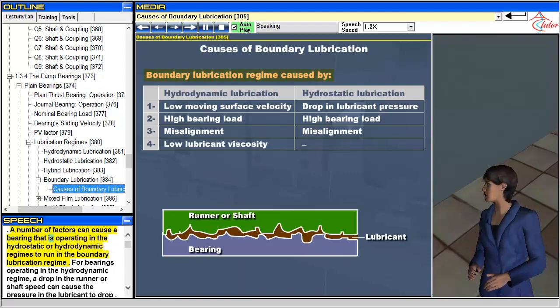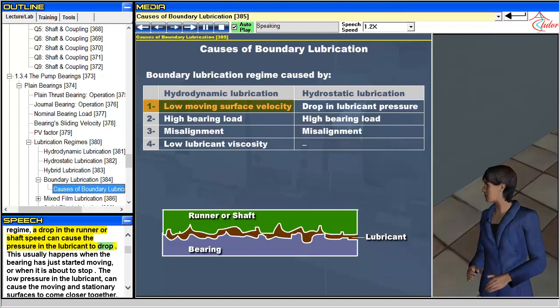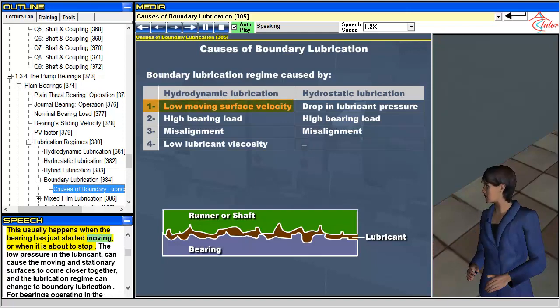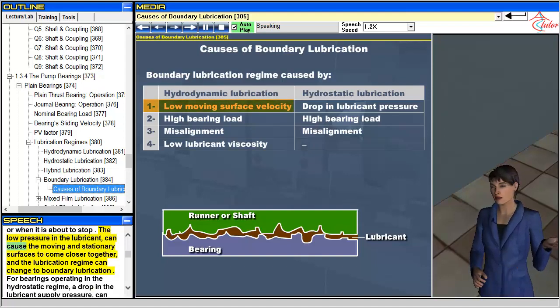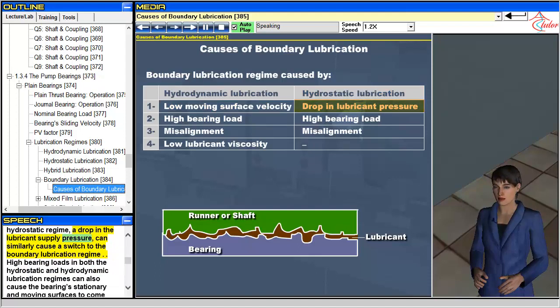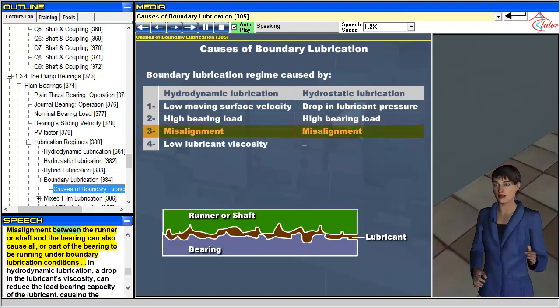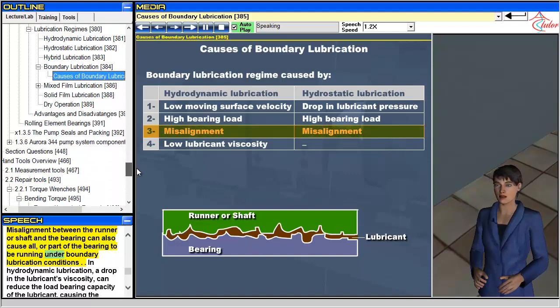Several factors can cause a bearing operating in hydrostatic or hydrodynamic regimes to run in the boundary lubrication regime. For hydrodynamic bearings, a drop in runner or shaft speed can cause lubricant pressure to drop, typically when the bearing starts or stops, allowing surfaces to come closer together. For hydrostatic bearings, a drop in lubricant supply pressure can similarly cause a switch. High bearing loads in both regimes can also cause surfaces to come closer together. Misalignment between the runner or shaft and bearing can also cause all or part of the bearing to run under boundary lubrication conditions.